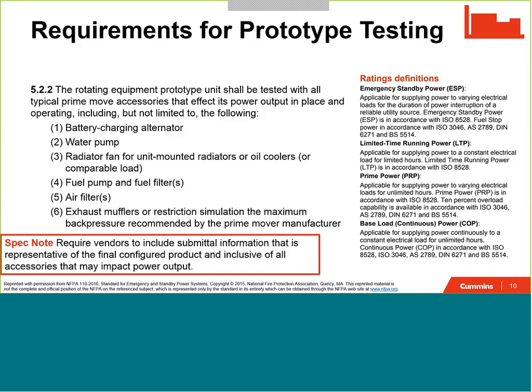On the right-hand side, what you're seeing is a description of the different ratings that the product complies with. And one of the key ones there is actually ISO 8528, which you see highlighted in each of those four rating definitions. It's important to note that ISO 8528 compliance because ISO 8528 specifically calls out prototype testing or ratings that are indicative or are inclusive of all of these parasitic loads.